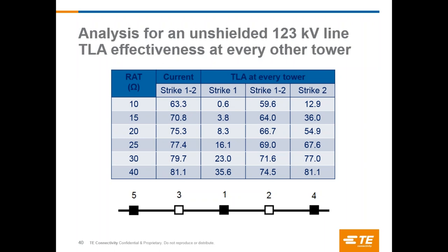As we cannot control the lightning discharge, lightning can happen at any point of the line, we can observe that installing line arresters at every two towers is not an effective method for improving the protection of the unshielded line for direct strokes, even in case of higher insulation. This method can be efficient for protecting the line against induced voltage. In this case, transient analysis shall be done to establish the optimum distance between line surge arresters.